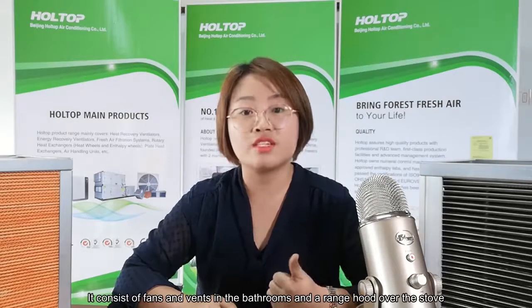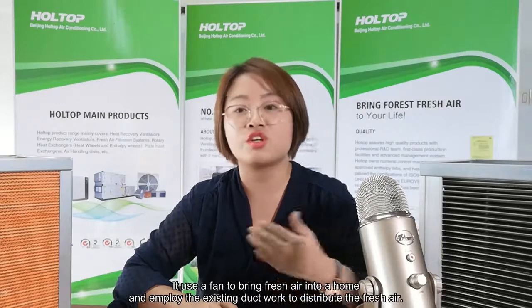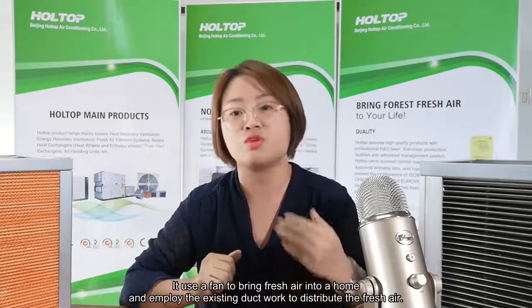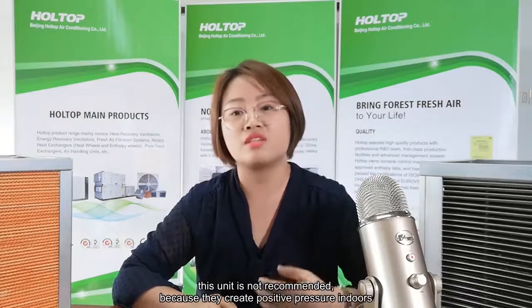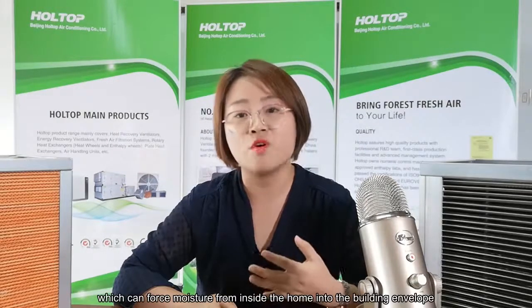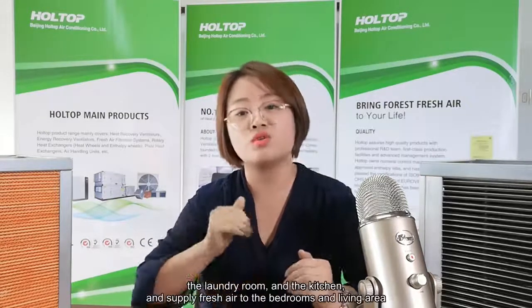We also have other types of ventilation. For example, the exhaust-only systems. It consists of fans and vents in the bathrooms and a range hood over the stove. Supply-only systems use a fan to bring fresh air into a home and employ the existing ductwork to distribute the fresh air. For some air-tight homes that require balanced systems, I think this unit is not recommended because it creates a positive pressure indoors. It can force moisture from inside the home into the building envelope. And also, for example, the balanced systems. They have the benefit of transferring the heat from the exhaust airstream to the supply airstream, lessening the amount of energy needed to heat the fresh air to room temperature. Typically, these systems pull exhaust air from the bathroom, the laundry room, and the kitchen, and supply fresh air to the bedrooms and the living area.